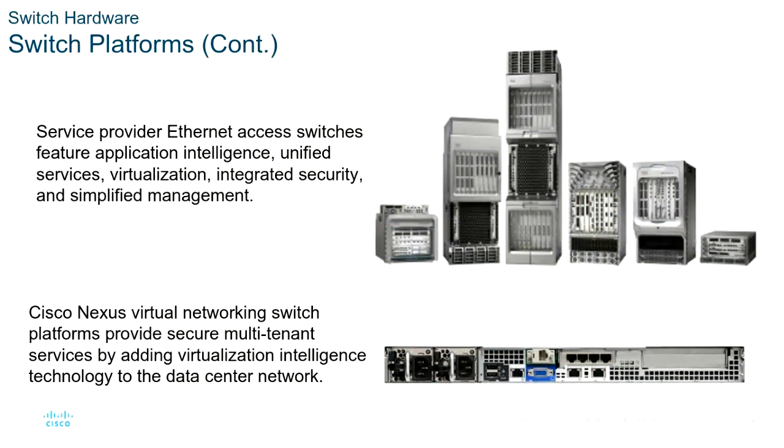If you look to the left part, it's kind of hard to see there, it's got 2 power supplies. It's got 2 plugs to plug in. So that way we have some redundancy. We can plug one power supply into one circuit breaker and plug another power supply into another circuit breaker, and at least have the ability of the switch to continue operating even if one of the power supplies fails. Or make one on the UPS and one on the commercial power.